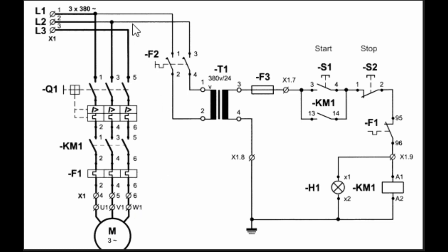Now we understand the power wiring, let's move to the control wiring circuit. Two-phase L1 and L2 are connected at the primary port of a step-down transformer which is used to step down the voltage from 380V AC to 24V AC.